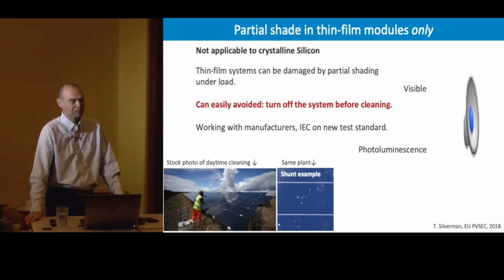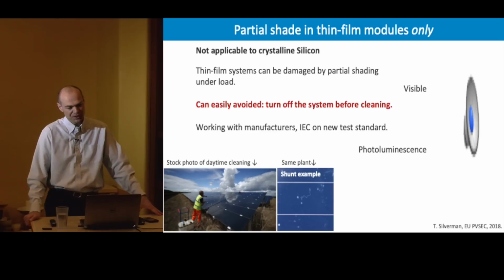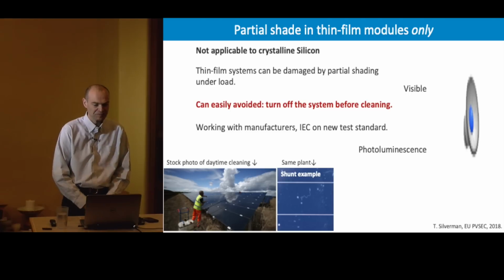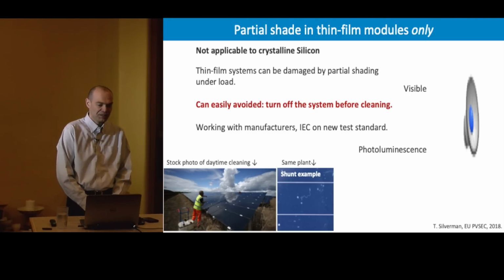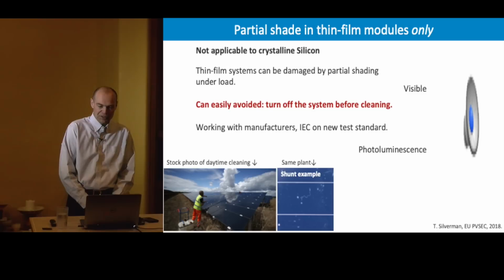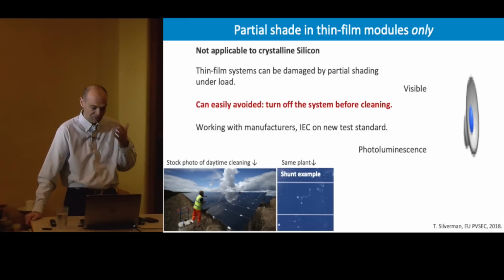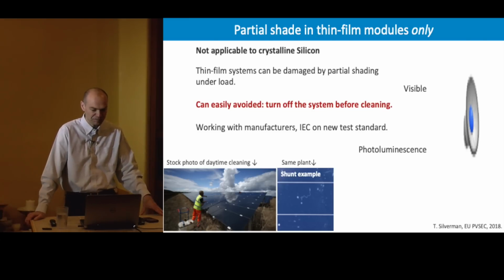Further, speaking of thin films, this applies only to thin films, and is not applicable to crystalline silicon, because you can actually create damage with partial shading when you clean these modules. This is all done by my colleague Tim Silverman.